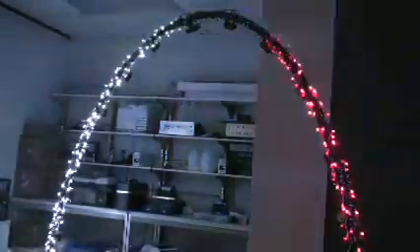So it significantly reduces the wire required to hook a system up like this, and it's all very low power LED. I had a system with 50,000 lights and it drew less than 2 amps of current on average — 4 amps maybe peak — averaging around 2, figuring most of the lights are off most of the time. Very energy efficient and a very flexible system.